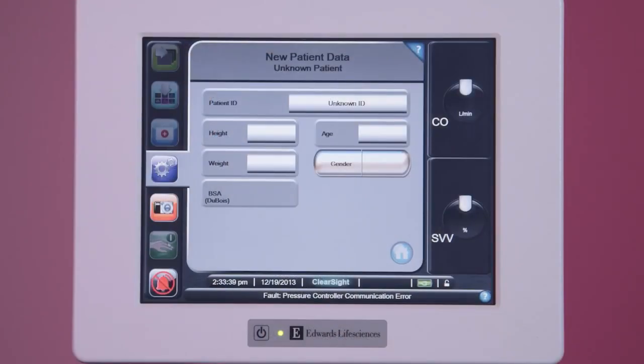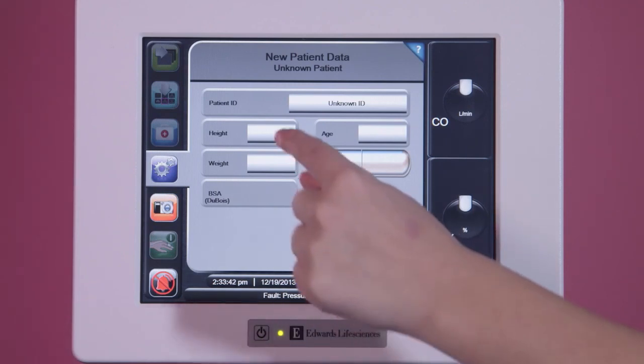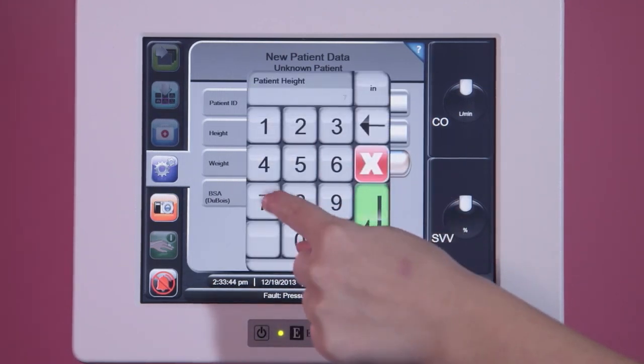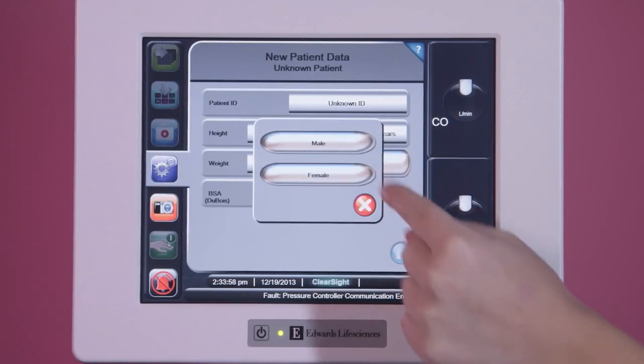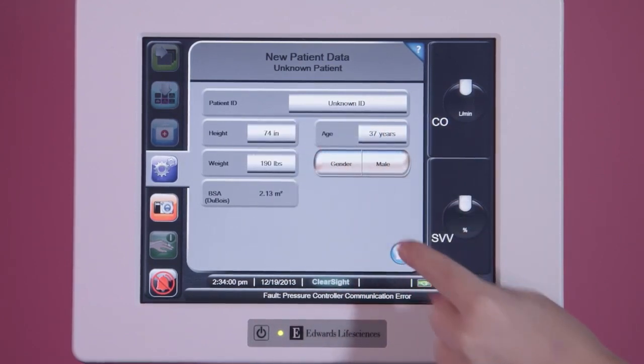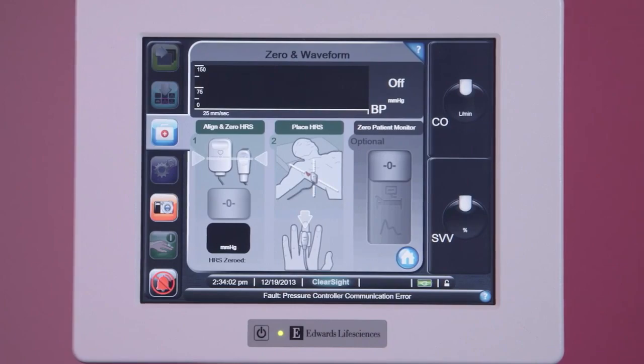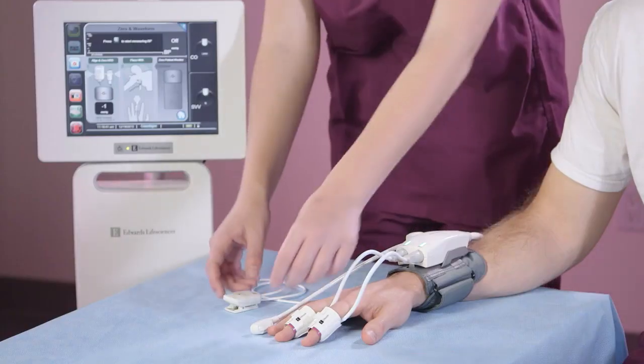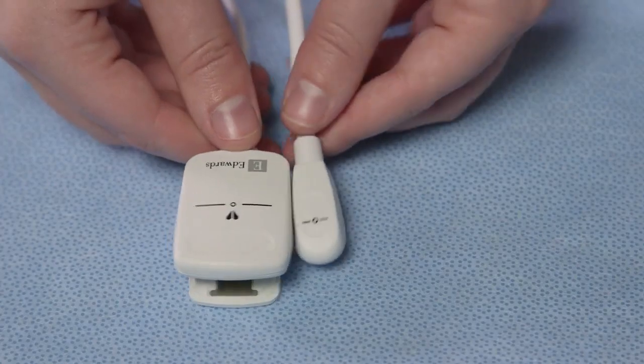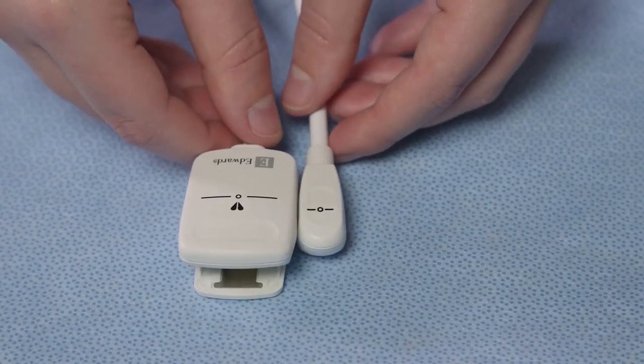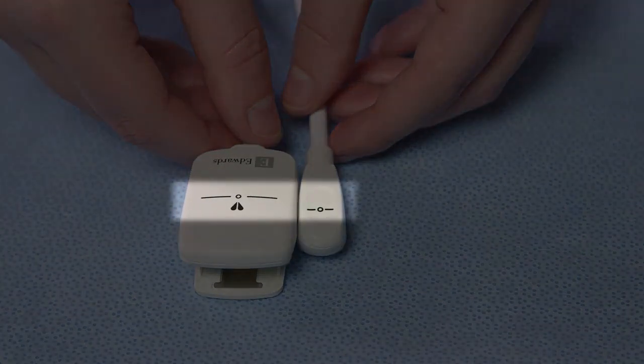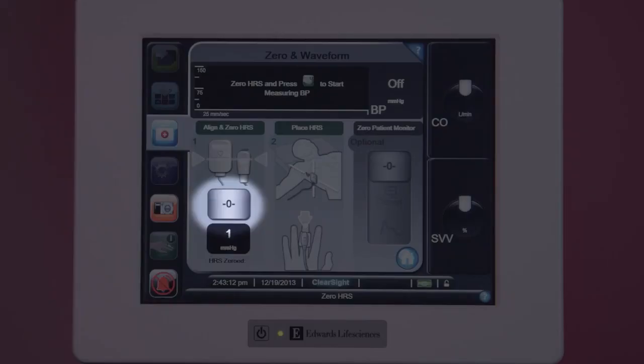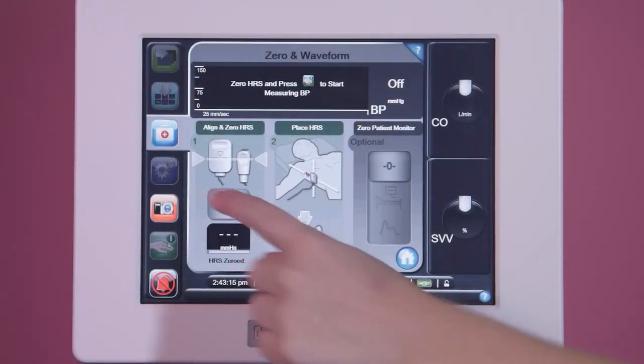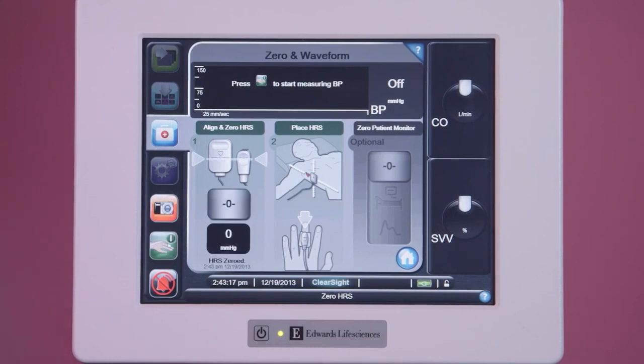Next, on the EV1000 monitor, enter the patient demographics on the patient data screen. Tap the Home button to confirm. The software will redirect to the zero and waveform screen. To zero the HRS, hold the finger component and the heart component of the HRS at the same vertical level, ensuring that the horizontal lines on each component are aligned. Tap the Align and Zero HRS button. When the system completes the zeroing process, the finger and heart component of the HRS can be connected.